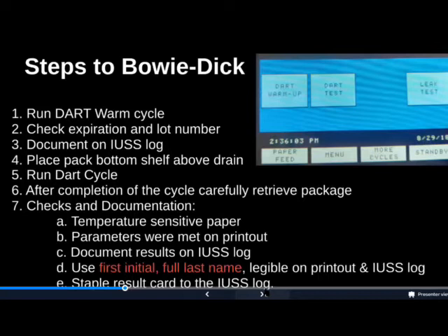Here are the steps to the Bowie-Dick, just an example of what it looks like, the warm-up test and the actual dart test. Run the dart warm-up cycle. Check the expiration and lot numbers always. Document on the IUSS log. Place the pack right above the drain on the bottom shelf. Run the dart cycle. After completion of the cycle, carefully retrieve the package.